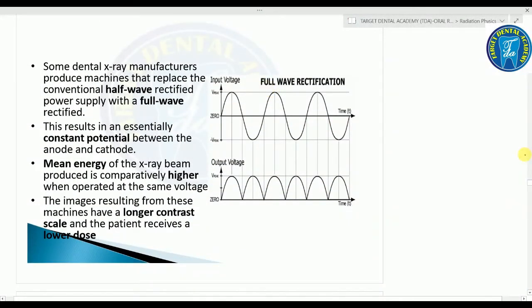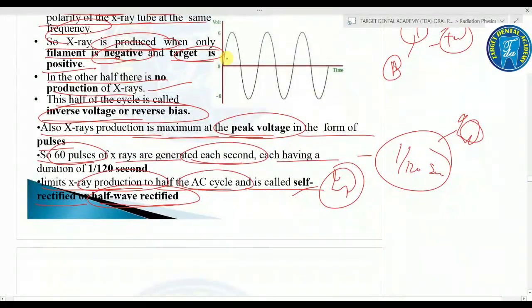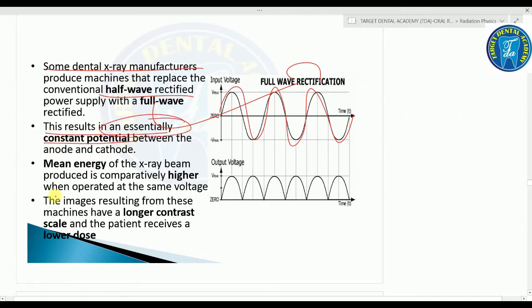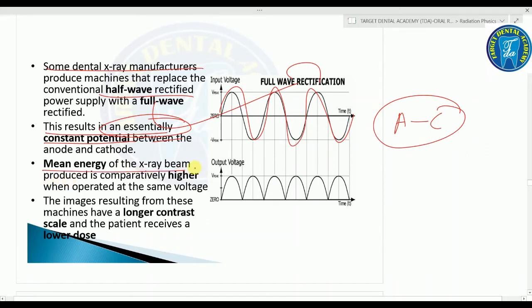Some dental X-ray manufacturers replace the conventional half-wave rectified with full-wave rectification. This results in an essentially constant potential between anode and cathode, and the mean energy of the X-ray beam produced is comparatively higher when operated at the same voltage.